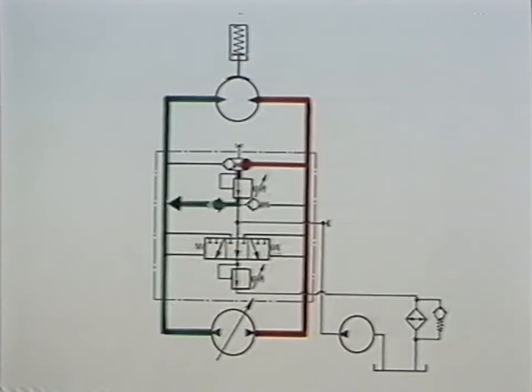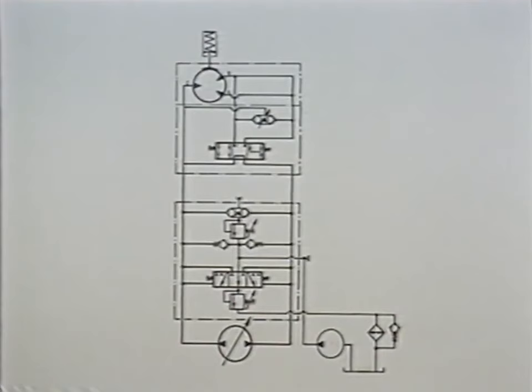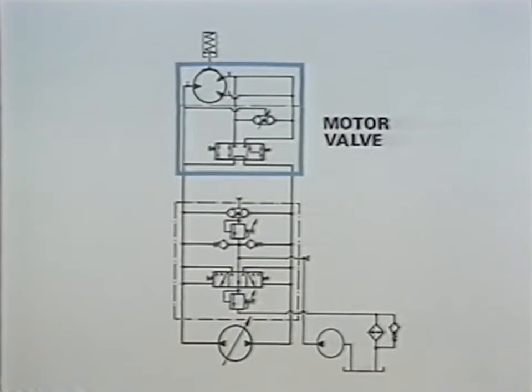Despite a very small specific flow of oil from the idling hydraulic pump, a corresponding flow must pass through the main circuit relief valve. To avoid unnecessary heating of the hydraulic oil and resultant excess wear of internal components, the system must be unloaded.